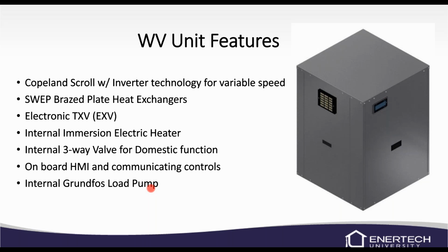The one thing that is nice about the electronic expansion valves is that we don't have the problem with them sticking like we do with the thermal expansion valve. They're driven open and driven closed by the head of that expansion valve with power. So if there's any kind of stuff in the system, it's not going to get stuck there, because that valve is powered open and closed, or it modulates. So we don't have to worry about them sticking. At least I have not heard of one sticking yet. I think we've had maybe one or two of the heads that go on top of it fail. But another thing that's nice about that is if the head were to fail, it's an electronic control. The head can be replaced without getting into the refrigerant circuit. So it makes it really nice.